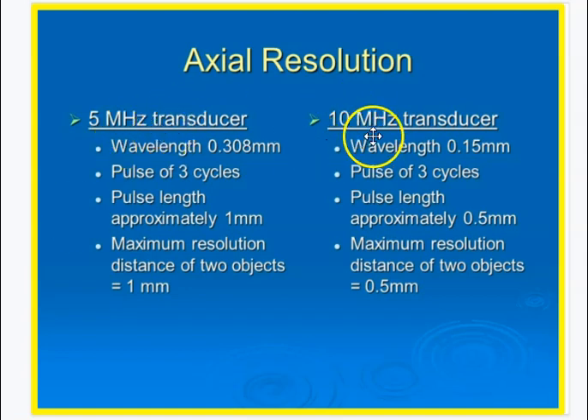If you compare a 5 and a 10 megahertz transducer, the physics is that speed divided by frequency gives you the wavelength. In a 5 megahertz transducer the wavelength is this, and in a 10 the wavelength is this. If you use the same number of cycles, the pulse length of approximately a millimeter is going to be about half of that. In a higher frequency transducer the resolution is going to be about half. So you can see the difference between a 5 and a 10 in axial resolution, and why a 10 megahertz transducer will separate objects a little better. The problem is that when you go up in frequency, you lose depth because of attenuation and so on.